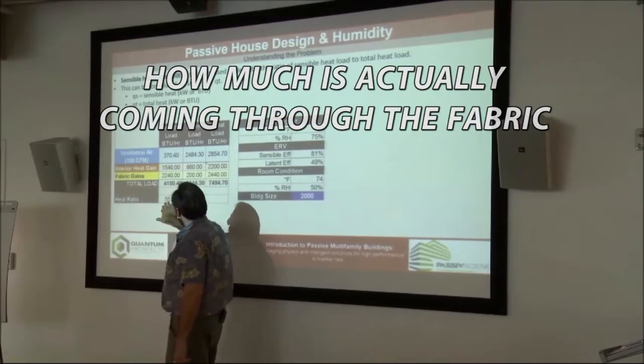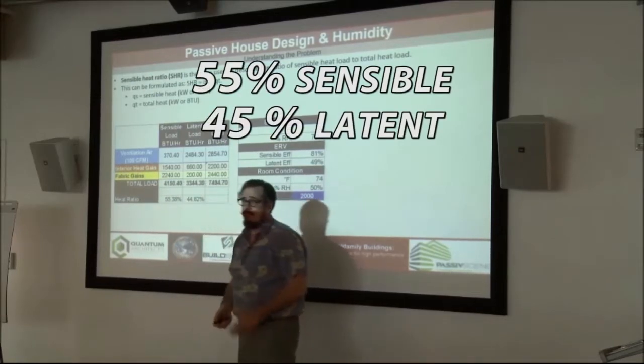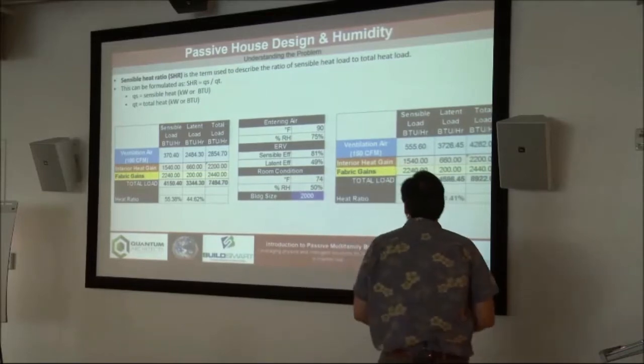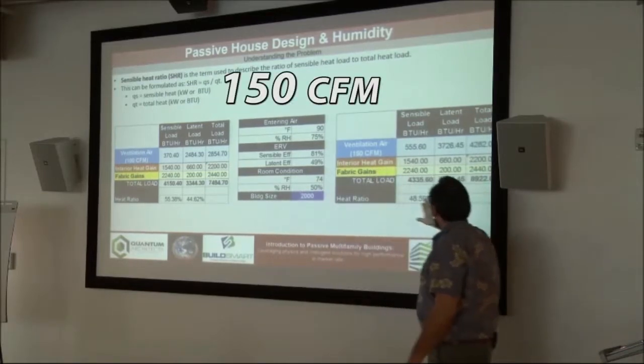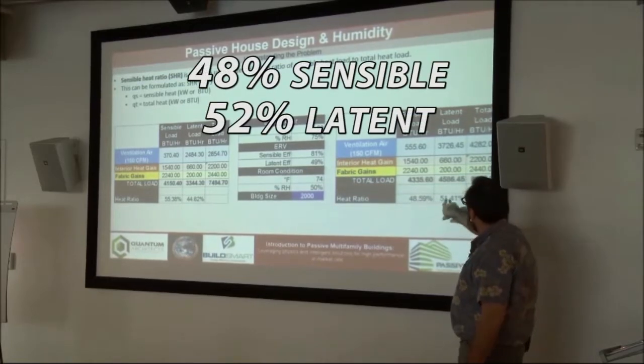Here's my total load. To get my heat ratio, we're at 55 percent sensible and 45 percent latent. Now I'm going to turn up the ventilation air to 150 CFM, and you can see that gets a little worse — it's now 48 percent sensible and 52 percent latent. That's for the 2,000 square foot building.